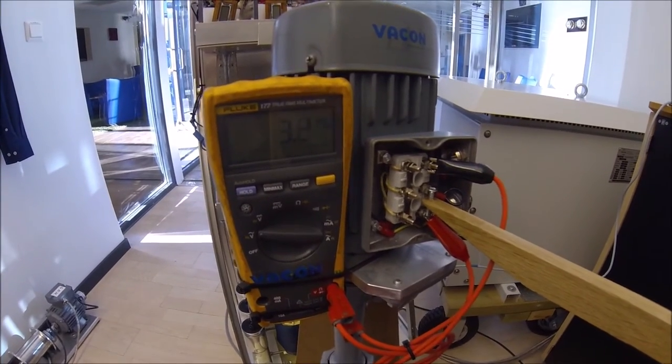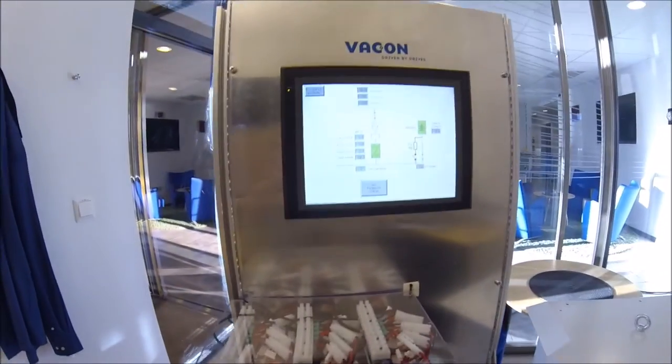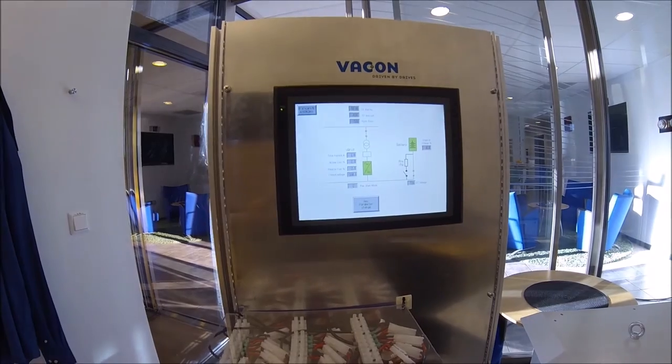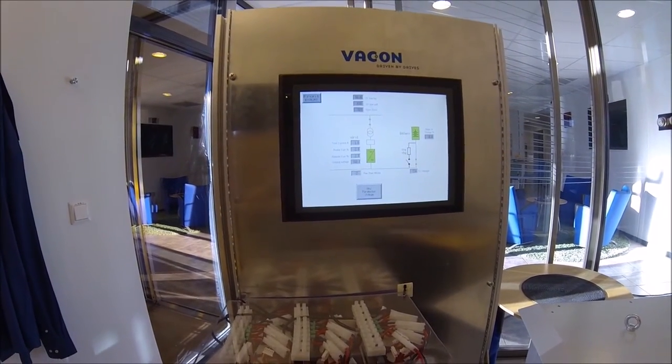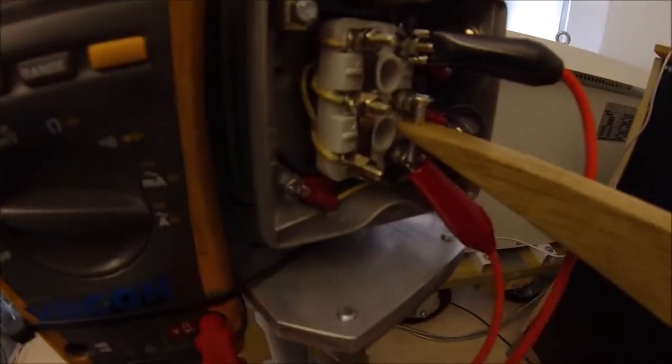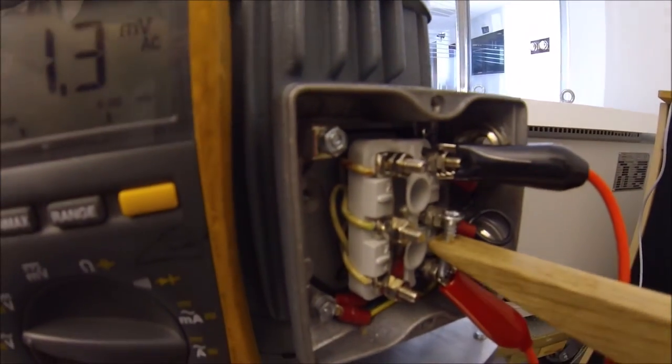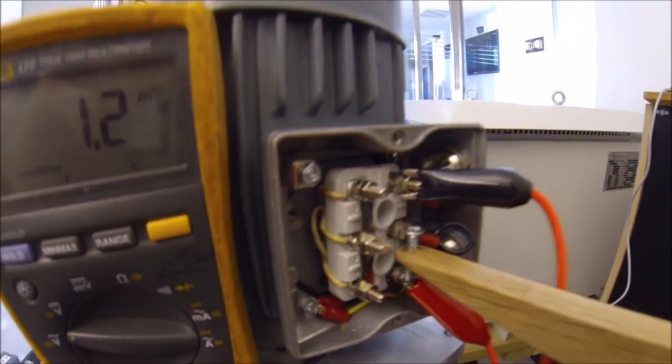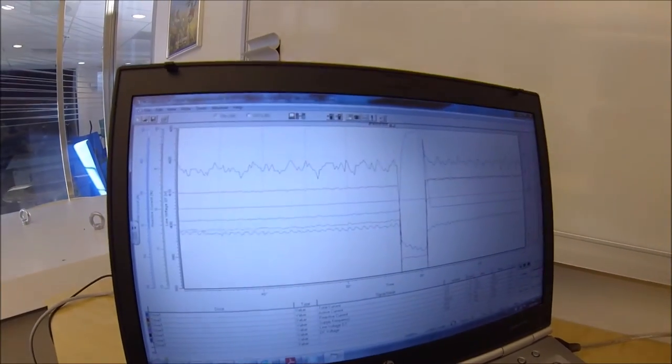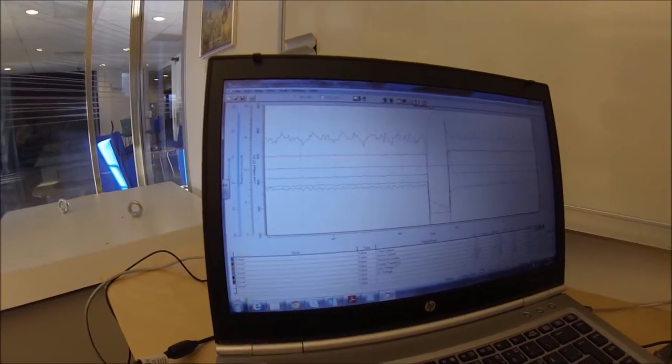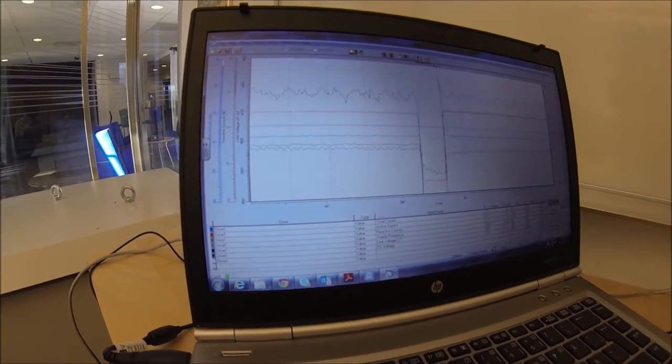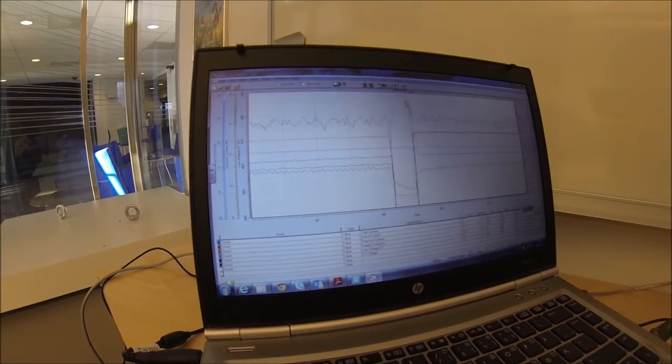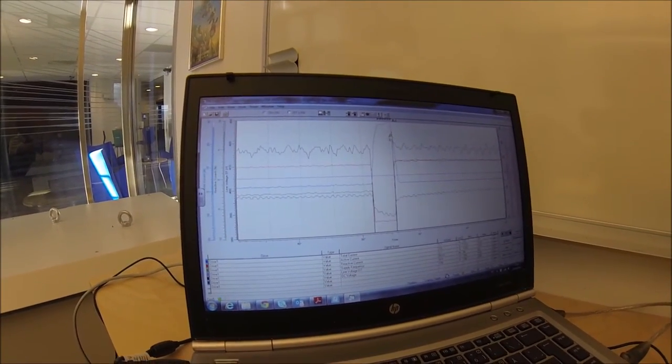We still have a short circuit and the drive is running okay so all the other distributors have got their power and the fuse for only this one has broken and we can see that the drive has put out a current just to blow the fuse.